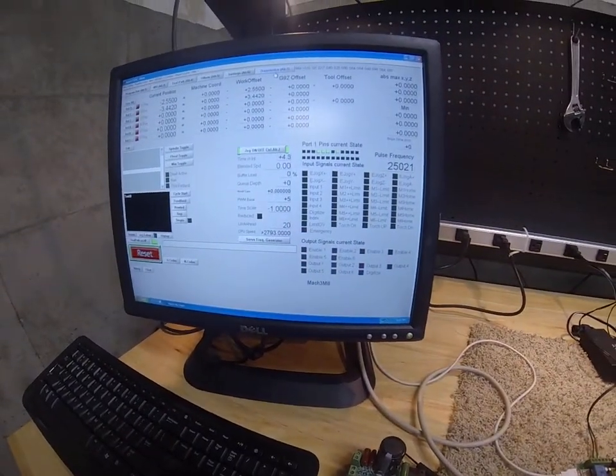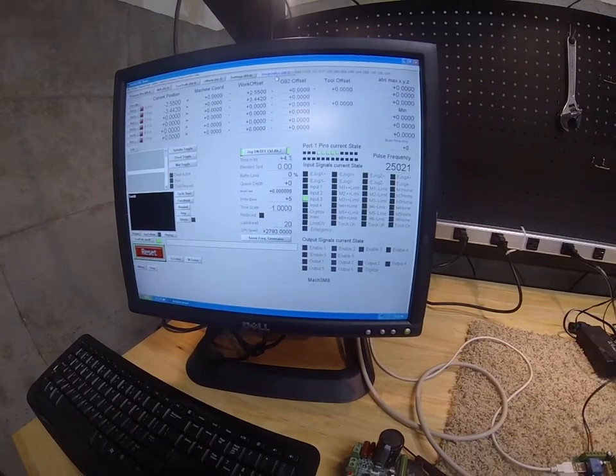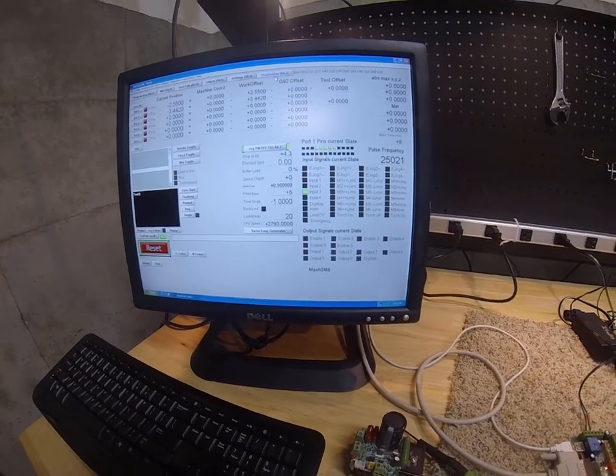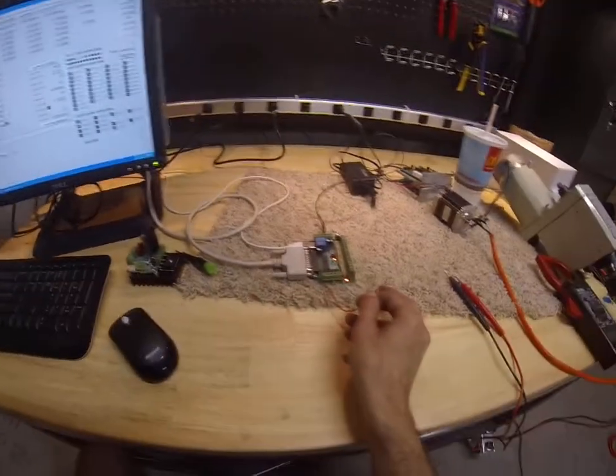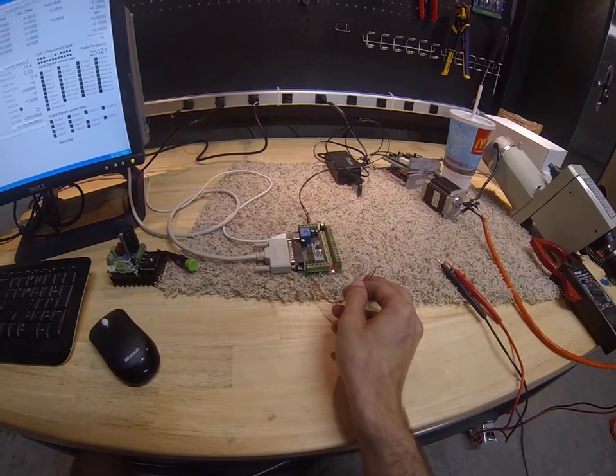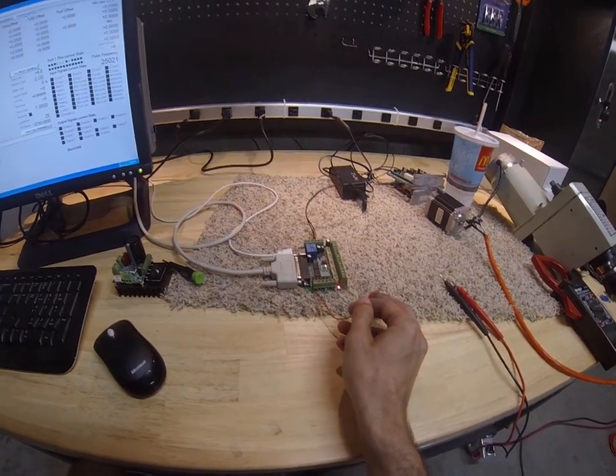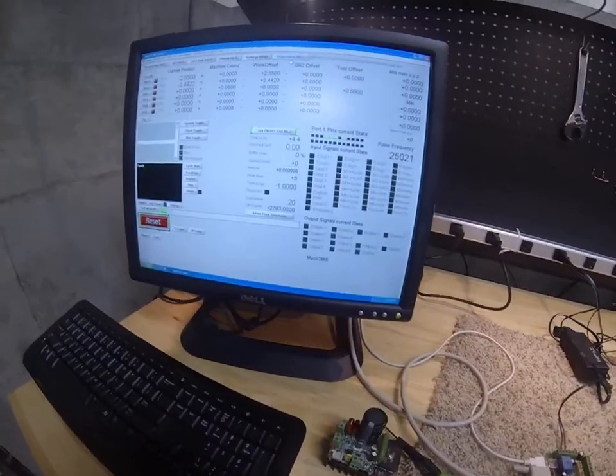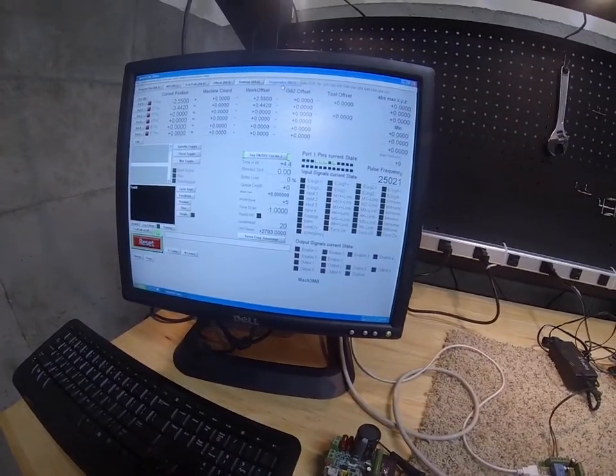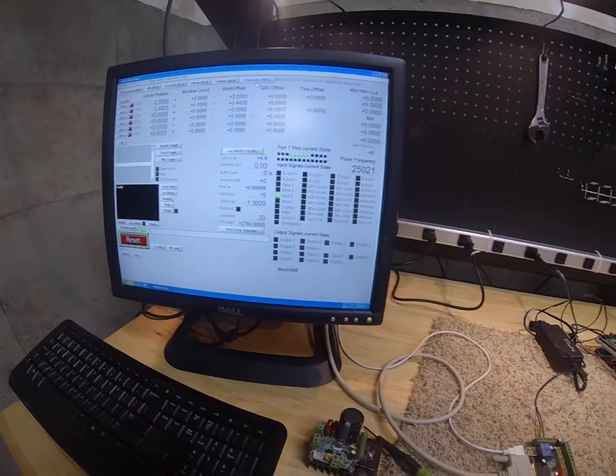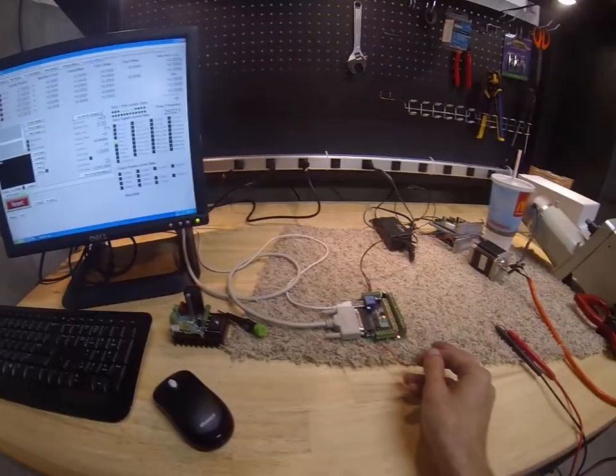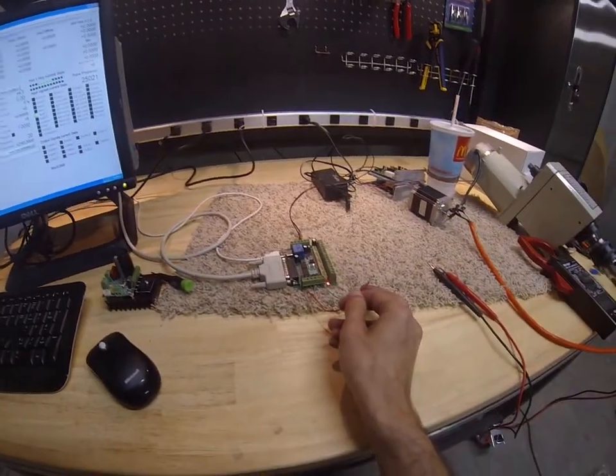So that's kind of how I prefer to do wiring. So when it's normally closed, the signal is not active. When it opens up, the signal becomes active. That's the way you do limit switches.